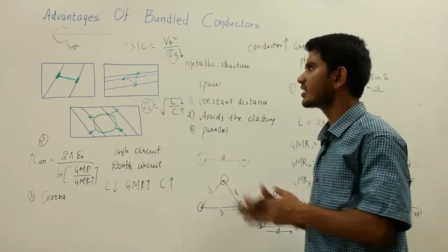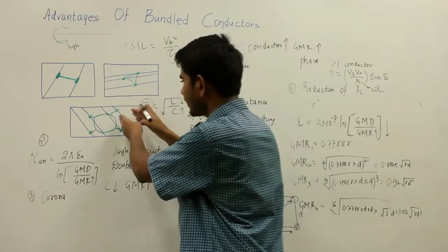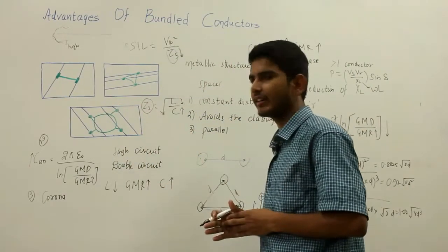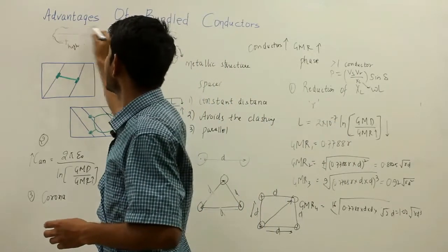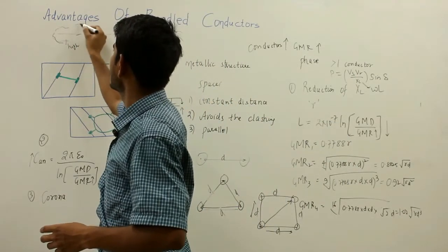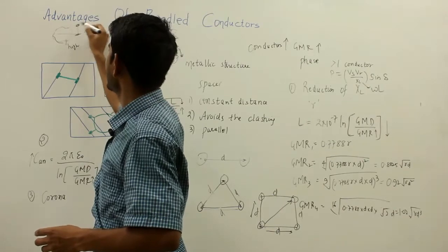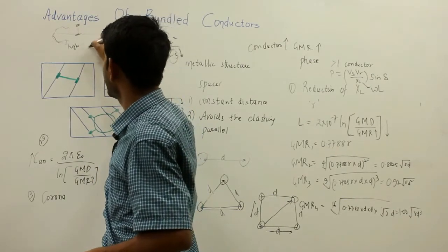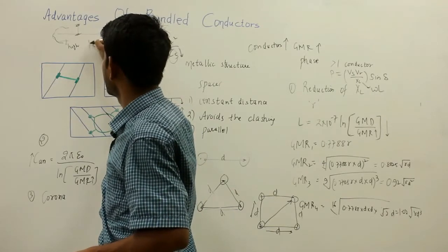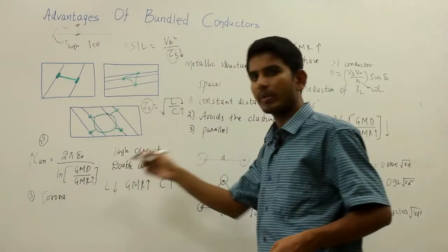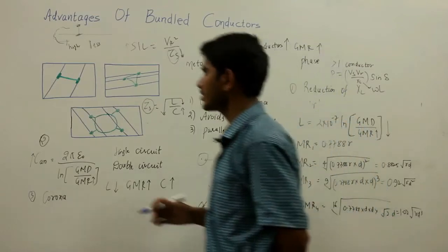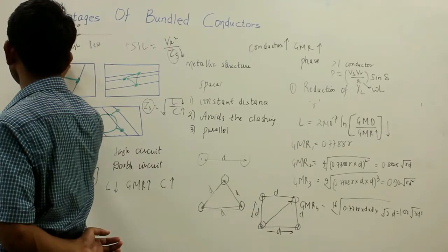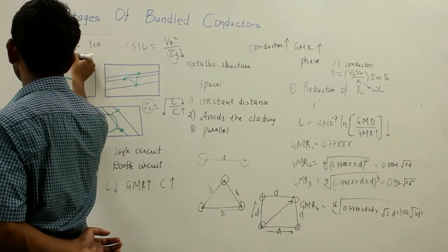Instead of using a single conductor, if you use conductors in close proximity forming a bundle conductor, then the voltage gradient will be less. If I use multiple conductors joined by spacers, then the voltage gradient is less, and this reduces the formation of corona.